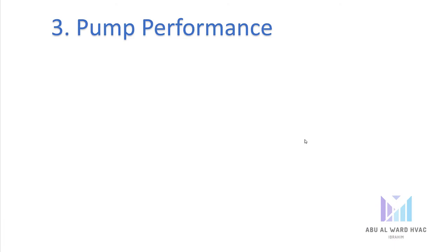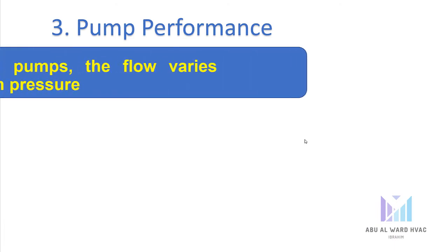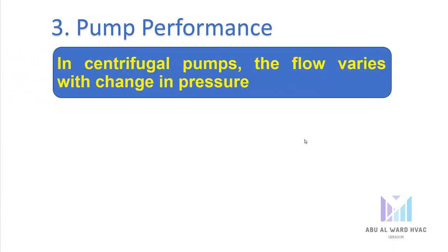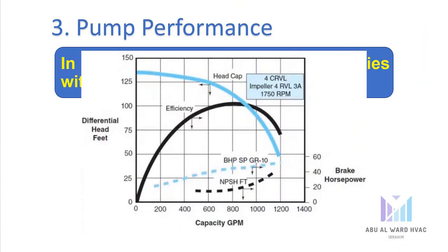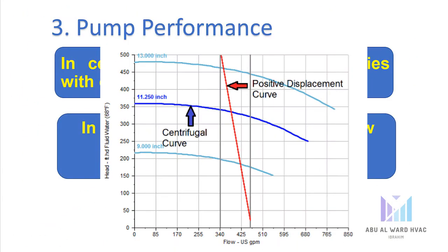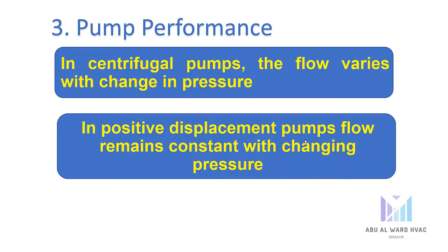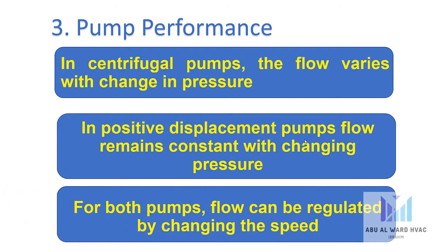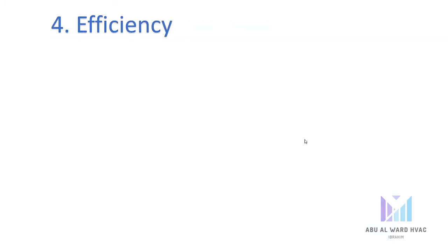The third aspect is pump performance. In centrifugal pumps, the flow varies with changes in pressure. In positive displacement pumps, flow remains constant with changing pressure. For both pumps, flow can be regulated by changing the speed.